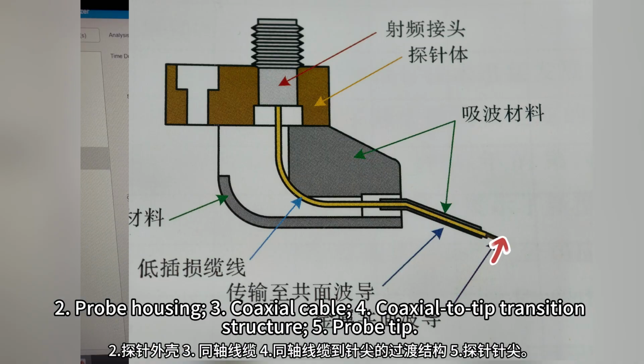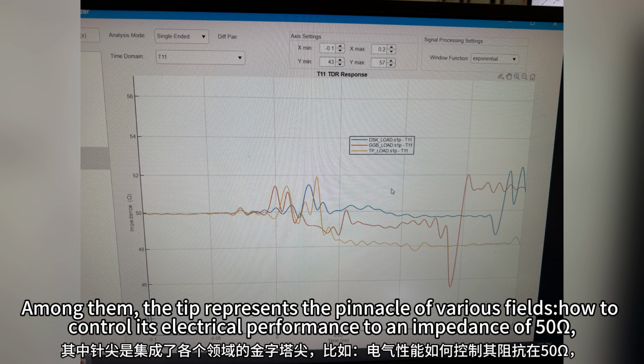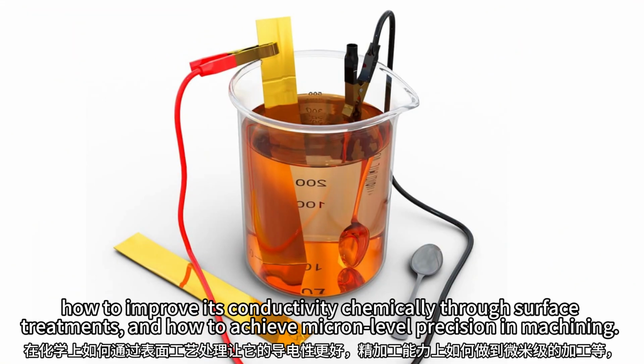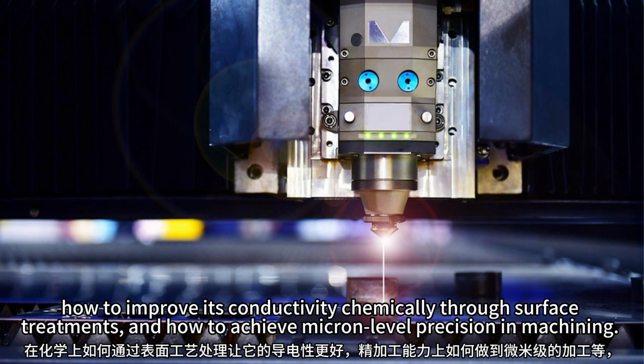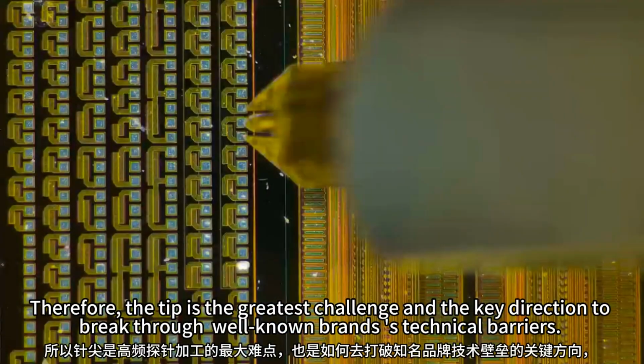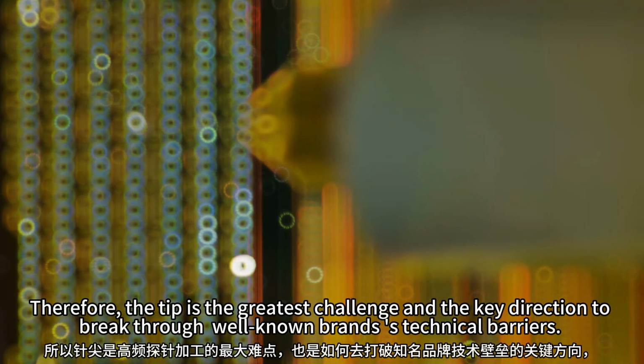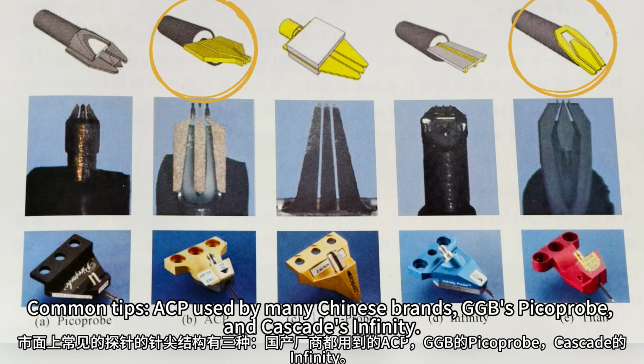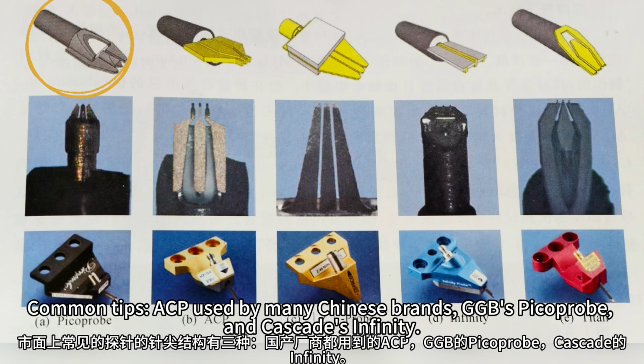5. Probe tip. Among them, the tip represents the pinnacle of various fields: how to control its electrical performance to an impedance of 50 ohms, how to improve its conductivity chemically through surface treatments, and how to achieve micron-level precision in machining. Therefore, the tip is the greatest challenge and the key direction to break through well-known brands' technical barriers. Common tips include ACP, used by many Chinese brands, GGB's Picoprobe, and Cascade's Infinity.